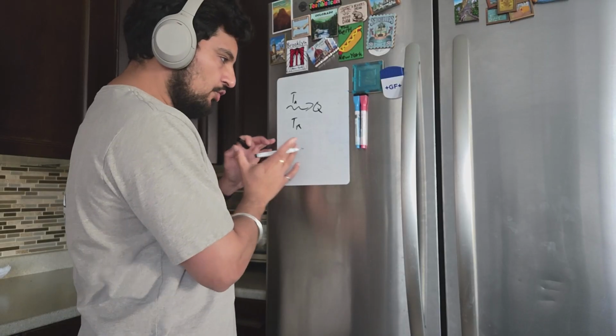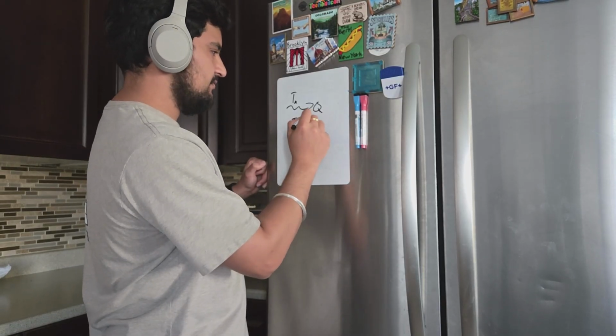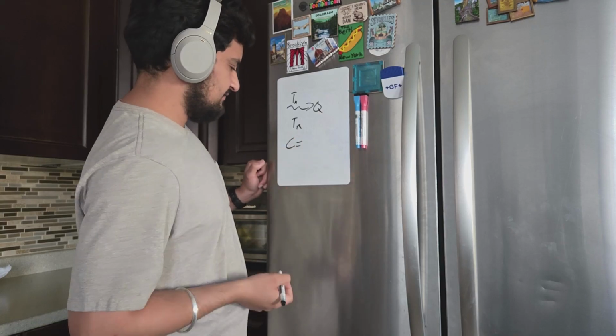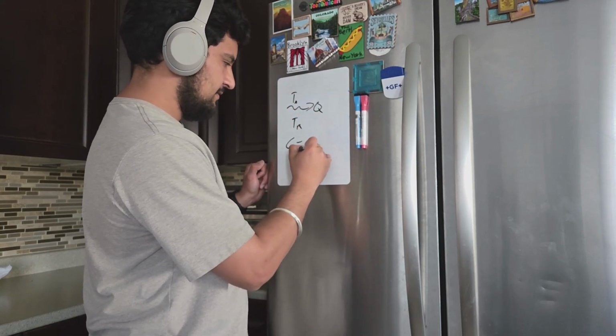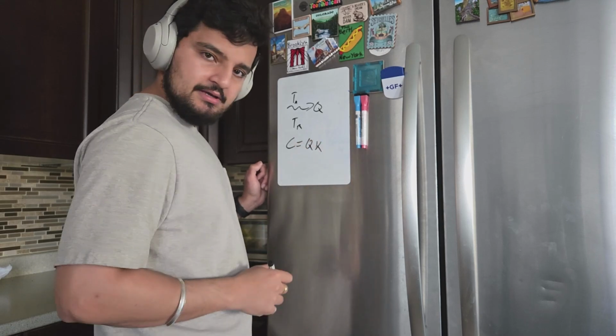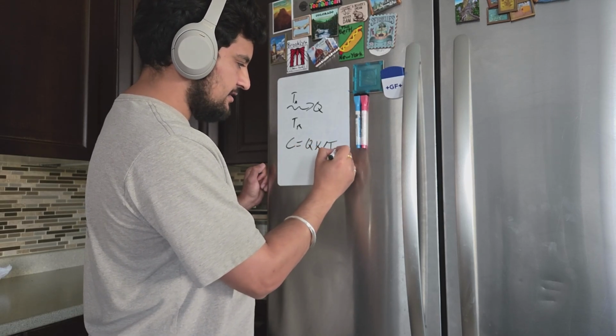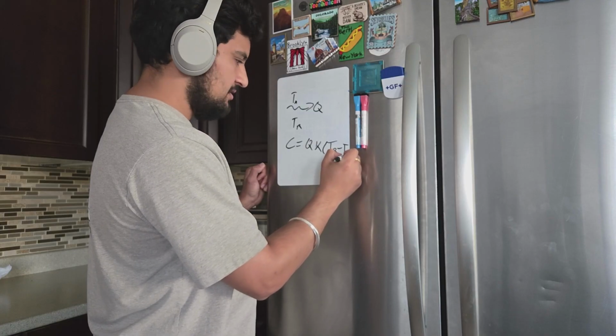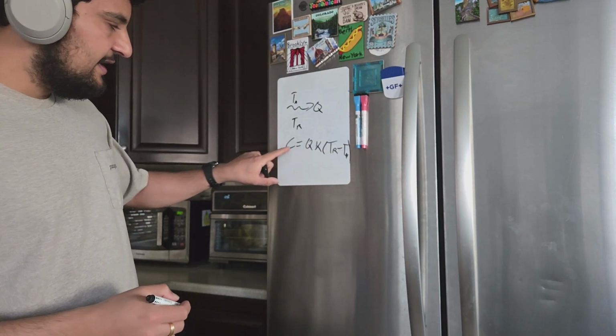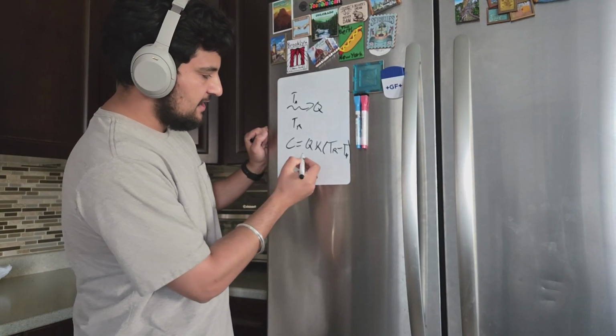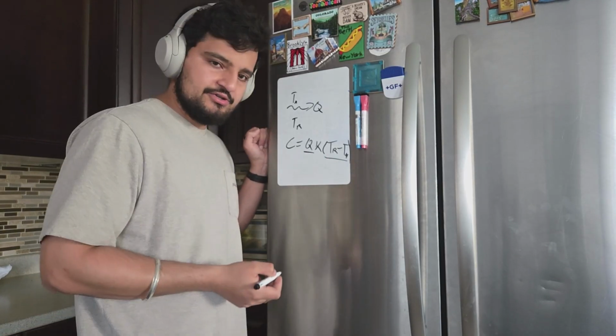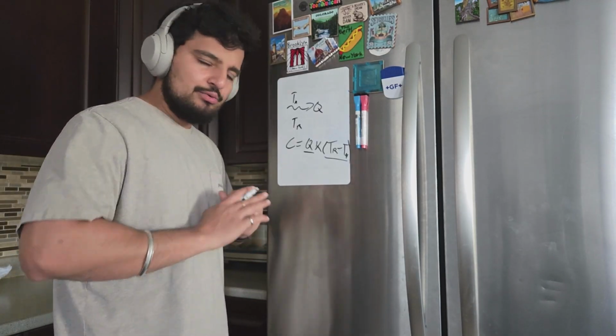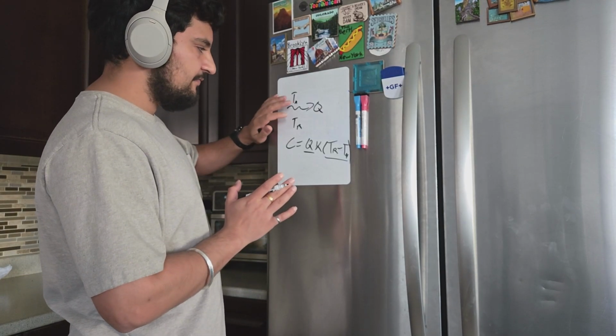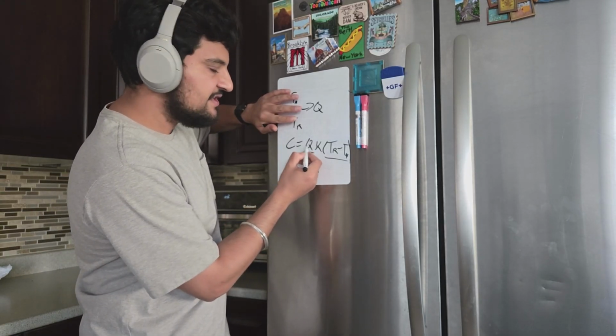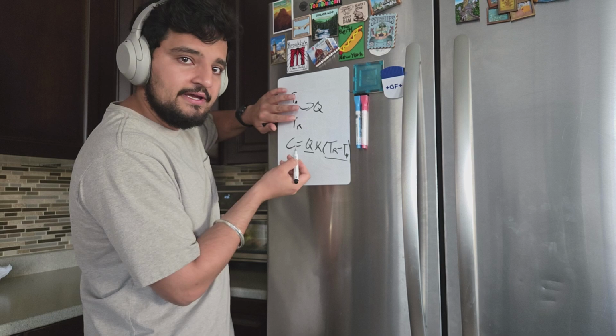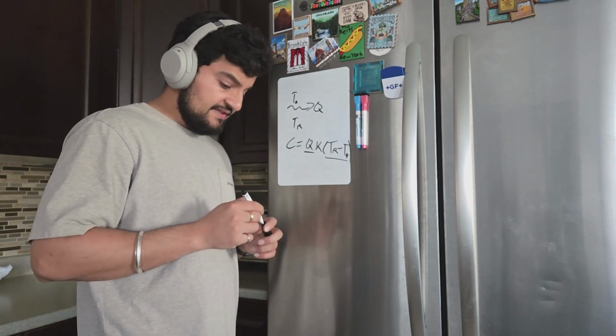Now the amount of cooling this air is providing is actually related to, so let's call this cooling C, is related to the airflow times some constant K times the difference between the room air and the supply air, right? So as you can see, the cooling capacity is dependent on the airflow and is dependent on the temperature differential. Now let's say your air conditioner condensers are working perfectly fine, so your air temperature is fine. If you reduce the airflow, you're going to reduce the amount of cooling that you're able to provide into that room. That's the key here.